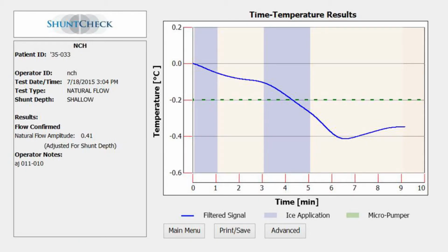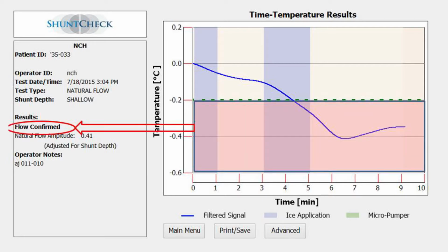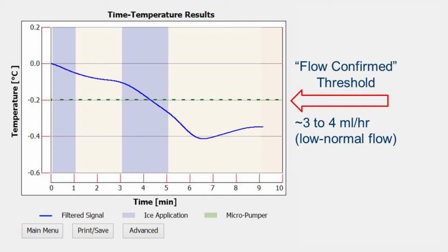results screen, a time temperature graph on the right, and patient-specific information on the left. This test shows a drop in CSF temperature, indicating flow. Anytime the temperature drop exceeds a threshold, ShuntCheck reports flow confirmed. Animal and bench testing indicate that this threshold corresponds to a flow rate of 3 to 4 milliliters per hour. That flow rate would be at the low end of normal, so flow must be at least at that level for ShuntCheck to report flow confirmed.